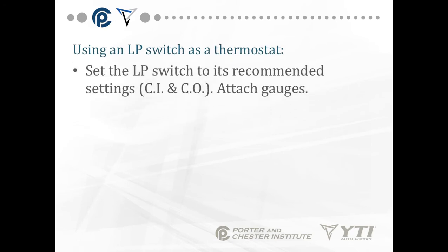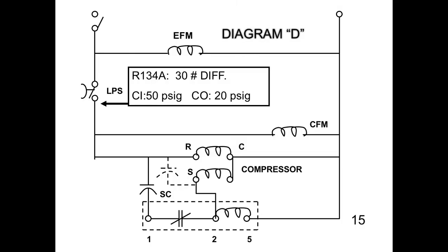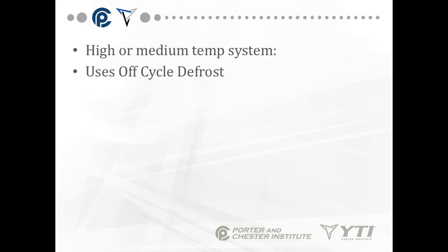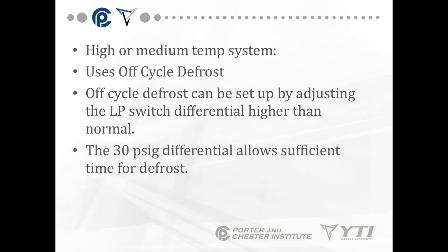To use a low pressure switch as a thermostat, set the LP switch to its recommended settings, cut in and cut out. Attach your gauges. Place a thermometer in the box and close the door. When the box reaches the desired temperature, set the cut out of the LP switch to the low pressure side shown on the gauges. So if I want my box temp to open at 20 psi, I also have to set a 30 pound differential. So my cut in will be 50 psi. High or medium temperature systems use an off-cycle defrost. Off-cycle defrost can be set up by adjusting the LP switch differential higher than normal. The 30 psi differential allows sufficient time for defrost. In other words, all we do is shut the compressor off for defrost. We keep the evaporator fan running.